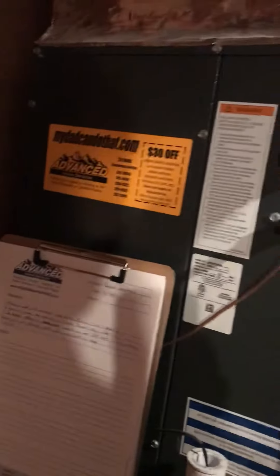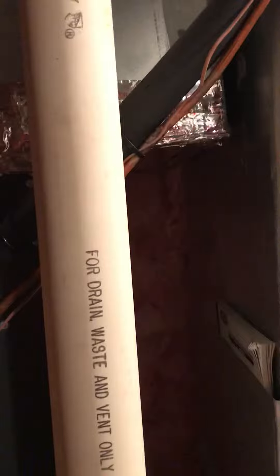The AC is fairly new and looks good, however I'm not a fan of this transition. Depending on how much room we have to work with — with the furnace being shorter — you could either pop it up on a small base can, or maybe we can create a better-looking transition, something slanted. Functionality-wise it's not bad, it's just we like to make our stuff look clean. I'll leave that up to you guys, whichever works best.